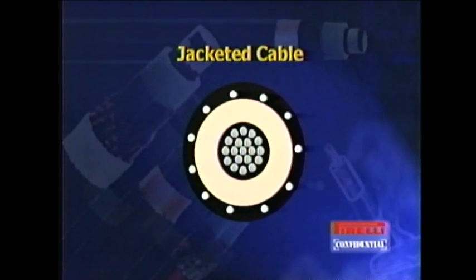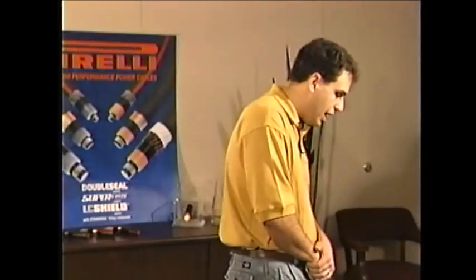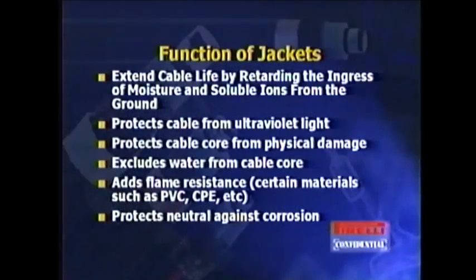Now, electrically, this normally serves no purpose, unless it's a semiconducting jacket, in which case it can serve as a constant ground. However, assuming the jacket is insulating, you probably won't have any electrical reason for it being there. It's mostly for mechanical protection. Some of the functions, of course, is to extend the cable life. The less chance you have of damaging the cable, the longer life you have with that cable.